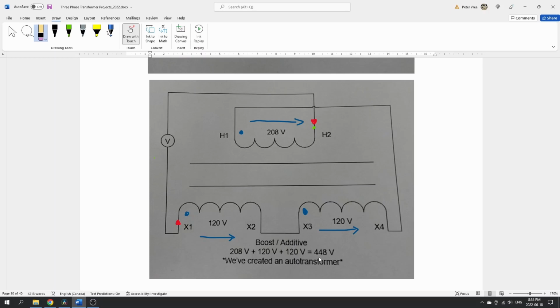Is it going to be exactly 448 volts? No, it's actually going to be a little bit higher, and that's because I only have the voltmeter, a high impedance load in the circuit. So I haven't actually completed the circuit. I don't have any current flowing, so the internal resistance of the windings isn't going to come into play. So we're expecting to see the additive voltage: 120 plus 120 gives us 240, plus the 208 gives us a total of 448 volts. Okay, let's go back to the lab and see if that's what we get.